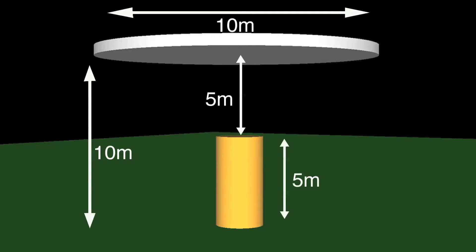Although in the lab it is not possible to reproduce a traveling wave of the magnitude that would be produced by a lightning strike, we can simulate the orientation and magnitude of the electric field component as it passes over the tank. A plane electrode made of a wire mesh and which is 10 meters in diameter is suspended 10 meters above the ground and 5 meters above a 5 meter high tank.